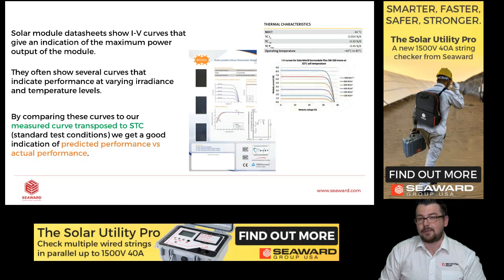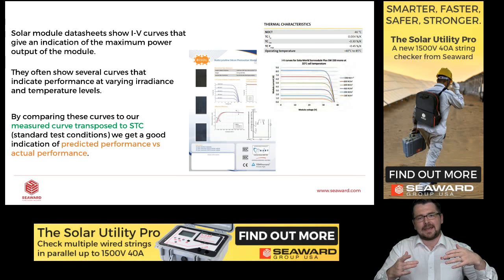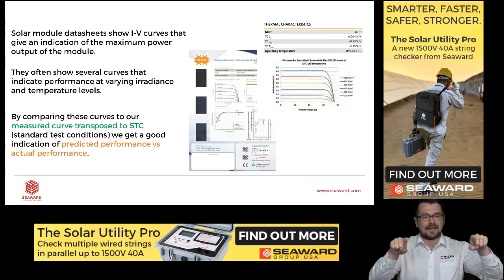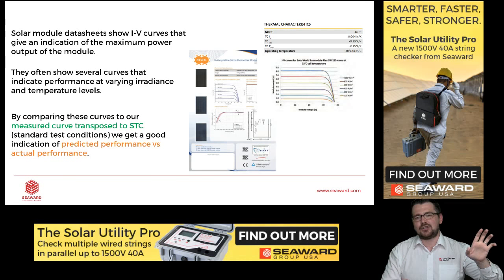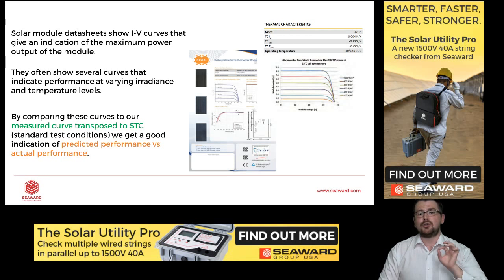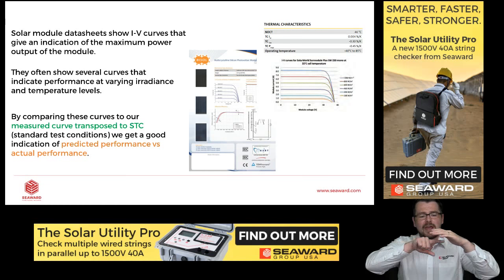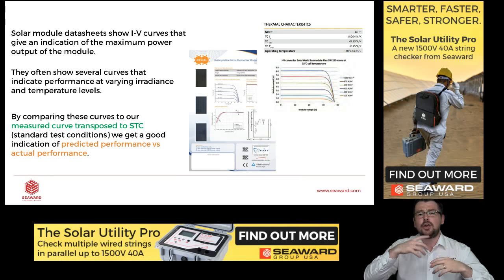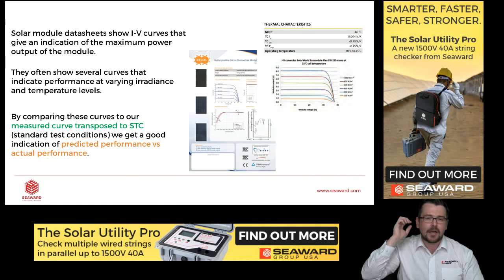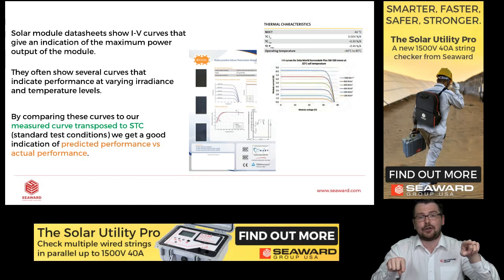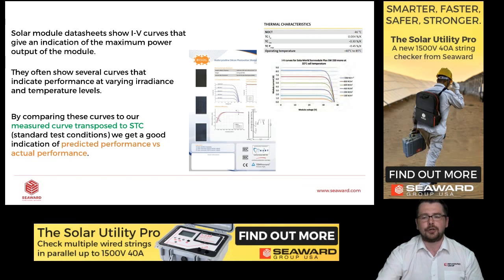So do be aware of that when you make your choice in buying panels, that what it says on the data sheet is actually probably nowhere near what you're going to get. But what we can do is take our measured data and transpose it to standard test conditions. Now, standard test conditions is 1000 watts per meter squared, 25 degrees Celsius. So if you're testing at 500 watts per meter squared, 12 degrees Celsius, we have to transpose that measured data using some clever algorithms, and that will generate our STC curve. And that's what our software can do for you.